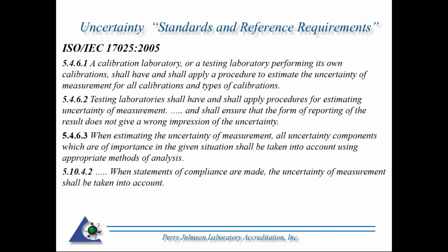And at 5.10.4.2, that is reporting the results. And one thing I did leave out here is when you need to either report the actual uncertainty and or a statement of compliance with your reporting of the results. We do specify in PL3 some of the requirements when you have to report uncertainty. And if you don't report uncertainty, what needs to be in place. But basically, what this is saying when making a statement of compliance, that is when you say something passes, fails, in tolerance, out of tolerance, that you have to actually take the measurement uncertainty into account prior to making that statement.